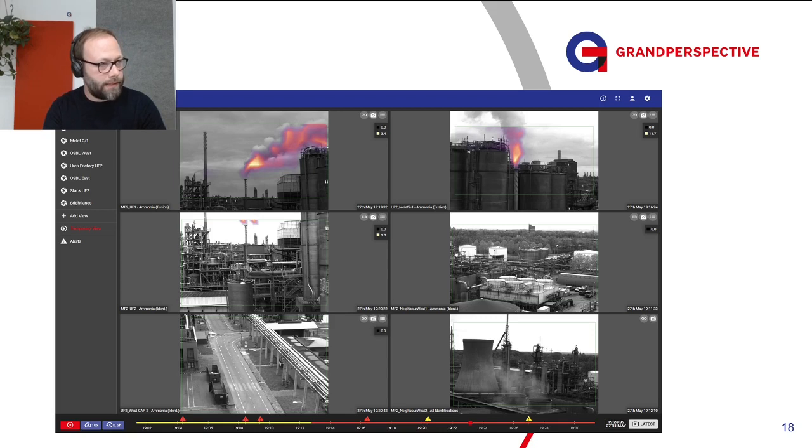And once a gas is detected and a chemical in the library is identified, you see here this example of the detection and localization of an ammonia emission. It is displayed over the video image, so the control room operator can intuitively understand where the gas emission is occurring, what the propagation direction is, and you can see the total amount in a false color display. And this amount value and the total size of the cloud, as well as parameters like the duration, for instance, are all scan area specific configuration levels for the alert generation.